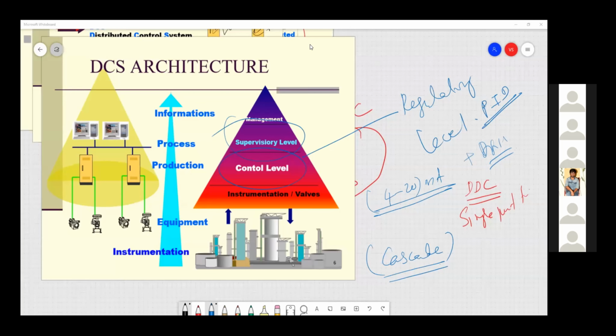So for 4 to 20 milliamps, current is always preferred for long distance communication because it's less susceptible to noise. That's the main advantage. Suppose you are transmitting a signal by means of voltage, it will have many pickups, electromagnetic pickups, so the amplitude will distort as distance increases. You may not get the original signal. So a lot of issues may happen if you transmit using voltage for a long distance. Instead, people always use current transmission.